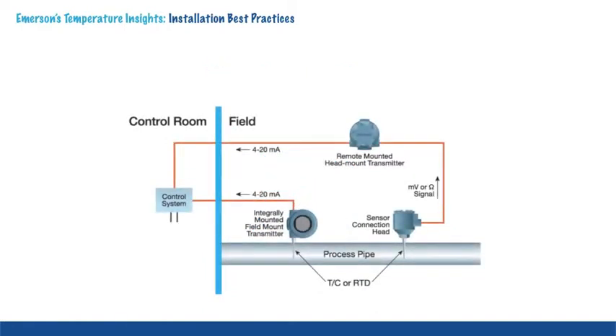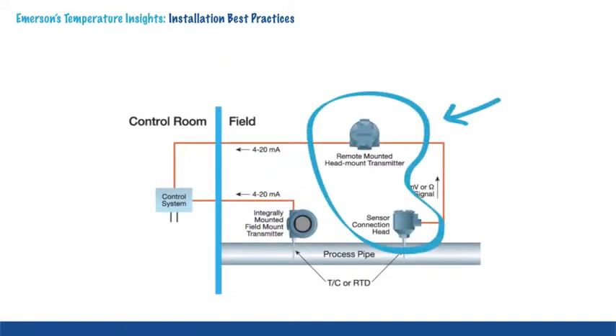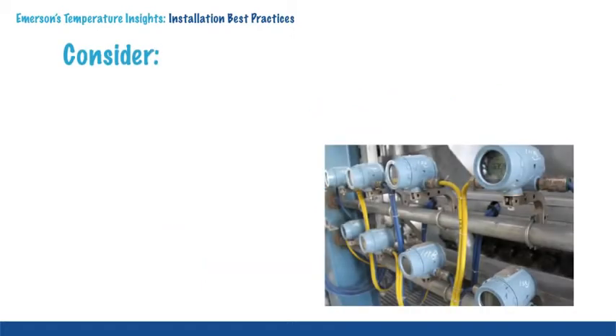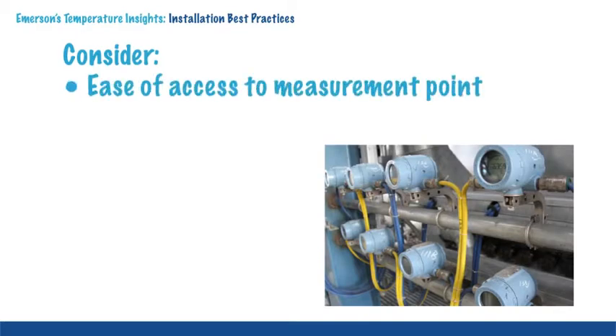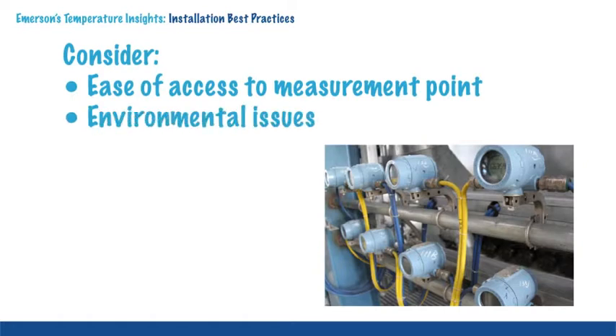Direct mounting will improve noise immunity due to sensor leads being shorter and thus less exposed to environmental interference. Transmitters can also be mounted remotely but in close proximity to the sensor and Thermowell assembly. When selecting the mounting location, consider ease of access to the measurement point, including the LCD display and environmental issues such as vibration, corrosion, and ambient and process temperatures.